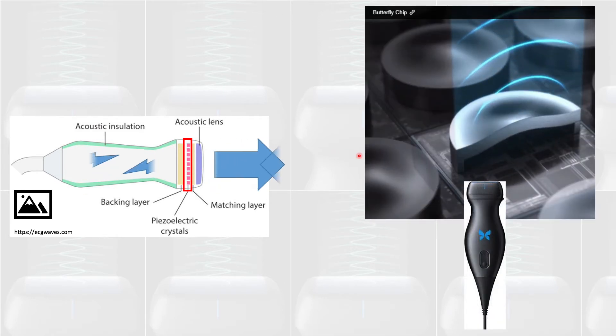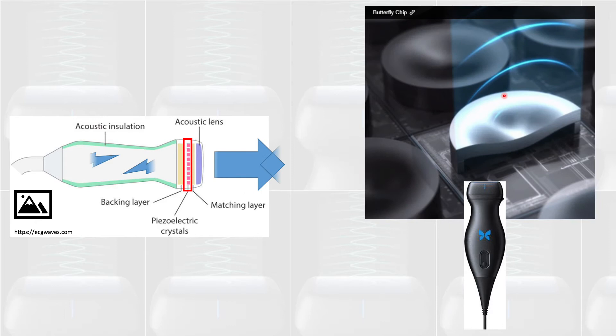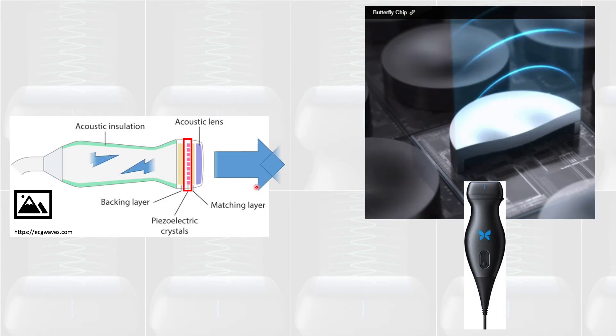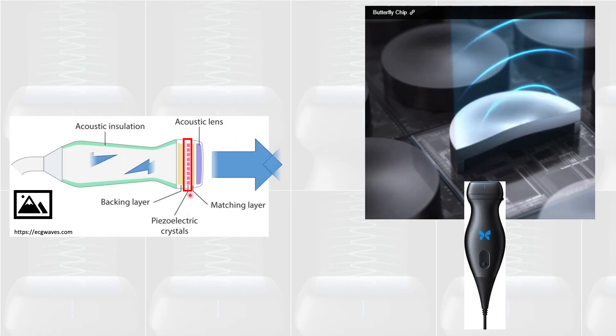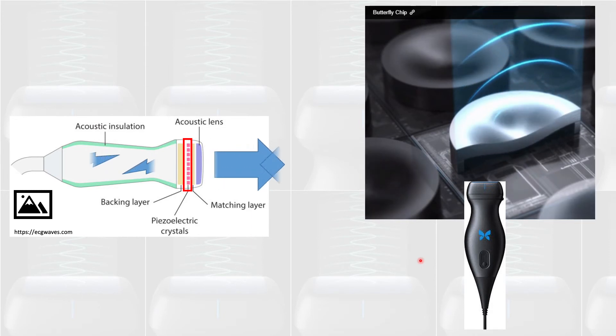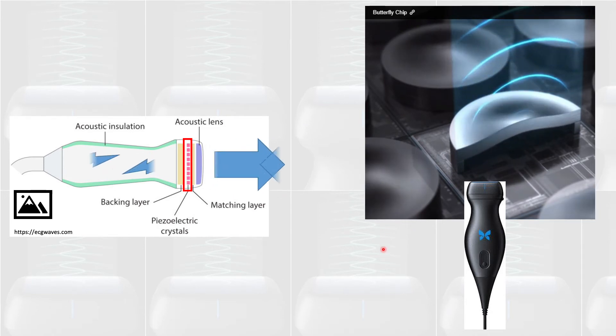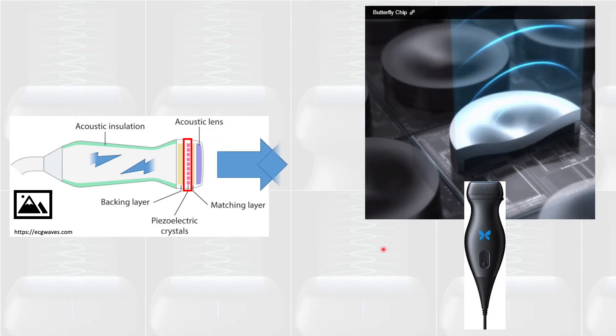The electric activity is sent to the screen and converted into the images you see on the ultrasound. That's a simple explanation of how you get the image. One thing about the Butterfly mechanism is that it actually uses a chip instead of piezoelectric crystals, which is one reason the price was lower when they launched the Butterfly IQ in 2017.